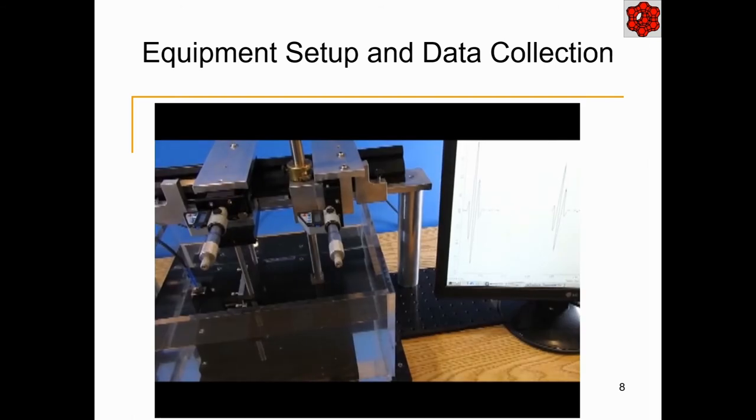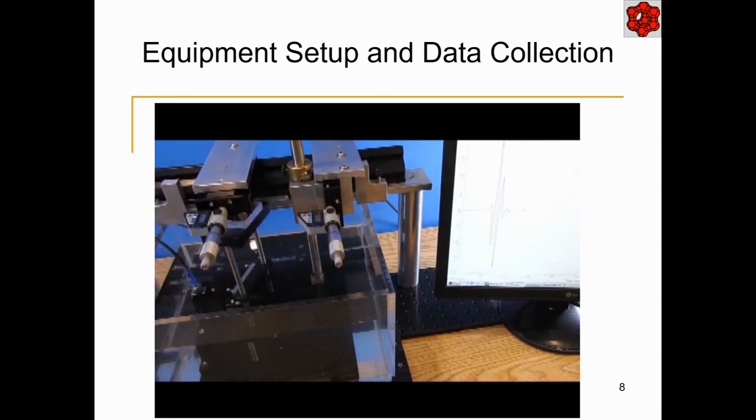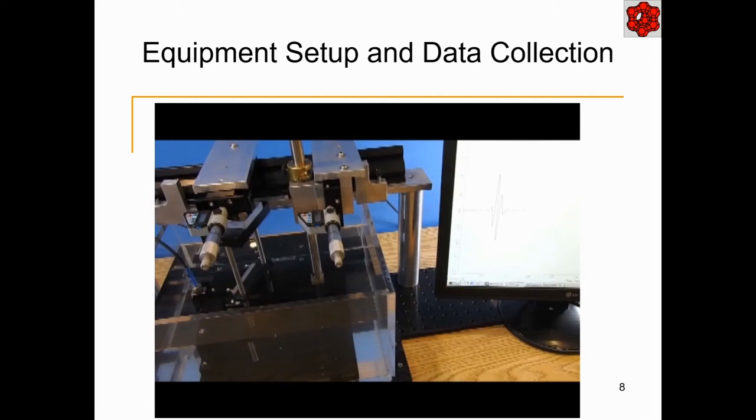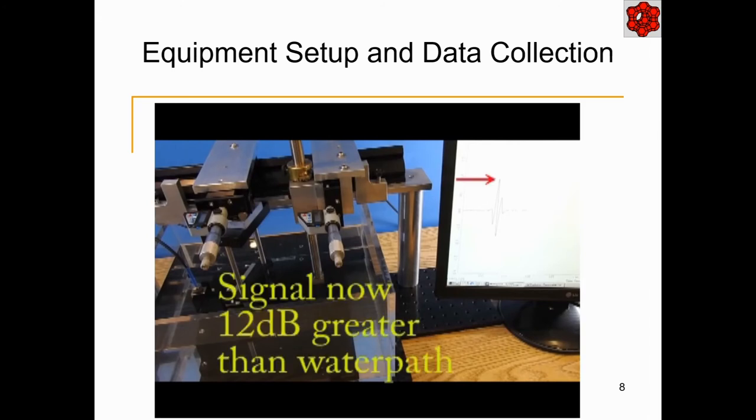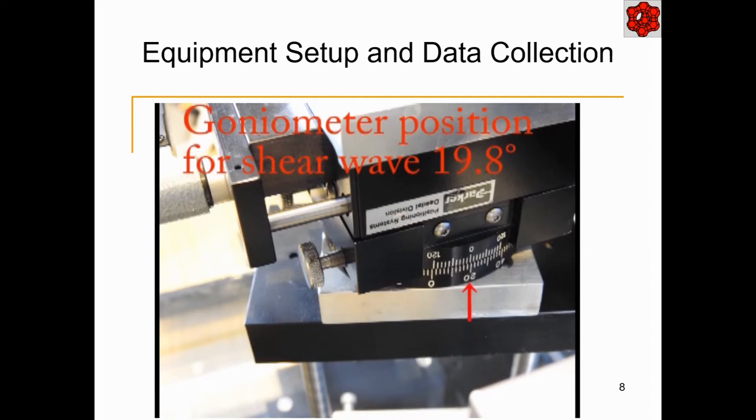Without removing the sample, rotate the goniometer while observing the A-scan signal. Observe the signal from the longitudinal pulse drop as the sample is rotated, and then watch for a new signal to rise at a slightly later time than the longitudinal signal had occurred. This new signal will be the result of the shear mode in the sample for materials that can support a shear mode. Carefully adjust the rotation until the signal is maximized. The L-mode should no longer be present because the maximum shear mode on its own will occur just after the first critical angle. Capture the A-scan and save it to a file noting the angle of rotation and the fact that it is a shear mode waveform.